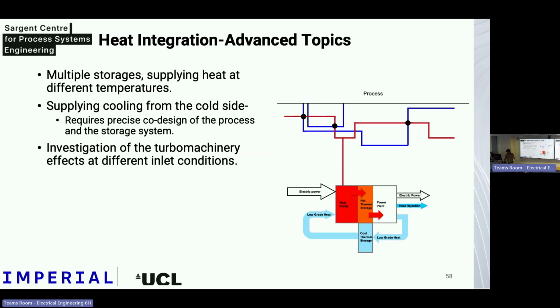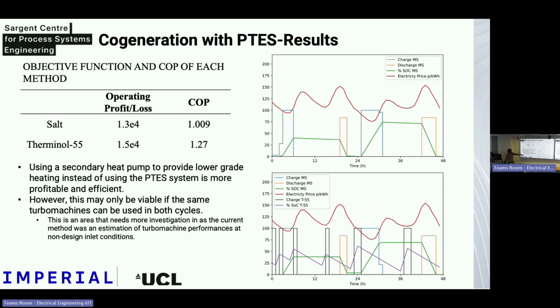In this case, the oil operates better. But if we have a system with different ranges of temperatures, for example, the oil goes from 250 to 350 degrees, but if we have a process with heating requirements from 250 to 350, but also from 350 to 450, then oil will not be able to supply that, and we will need to use the salt again for that higher temperature. So that's what we want to address - we want to hit as many of the temperature targets as we can, which gives us more cards to play with.